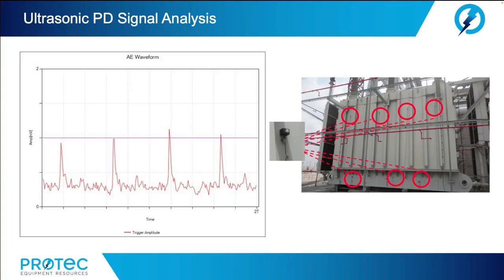The x-axis of the image spans 2 cycles of the power frequency, hence the notation 2T. Partial discharge activity will produce an ultrasonic emission each time the sine wave reaches a positive or negative peak. This means that in a 2-cycle time interval of approximately 33 milliseconds, there will be 4 ultrasonic pulses. The PD pulses have a short rise time and short duration. The peaks are tall and sharply rise above the noise floor. Typically, we consider the activity to be severe if the amplitude reaches greater than 10 dB at full gain setting.